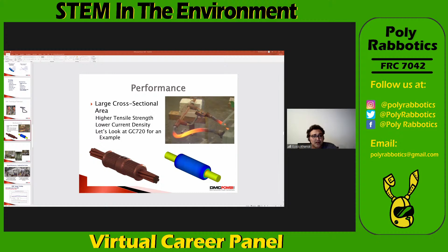Other tests are mechanical tests, like these tensile tests. Here is the fitting with the cable inside it. You try to pull it up while you are fixing it, to see how much load it can take. Here is another bus connector, and you do a tensile test on it. The test here to the right is called the heat rise test. We heat it to 100% of whatever the cable will be running at, then increase it to 125%, then to 150%. Every time we take the resistance, making sure the resistance and the temperature are not higher than the conductor. This is very important to give you an indication of whether it is good enough or not.